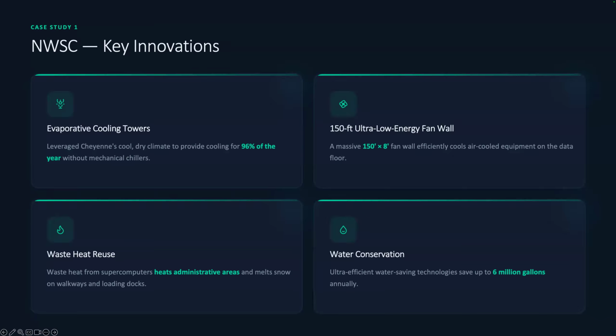With zero blowdown, we can also drive our pH high—the water at NWSC is around pH 9.5—which greatly reduces the amount of biological biocides and things you have to use, so you don't have to replenish the water. There's also a massive filtration system, because a lot of the dissolved solids precipitate out into magnesium and salts and other things that we filter out. But it saves about 6 million gallons a year, so it was considerable water savings.